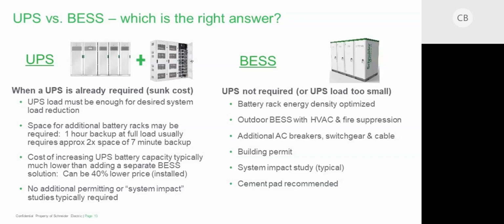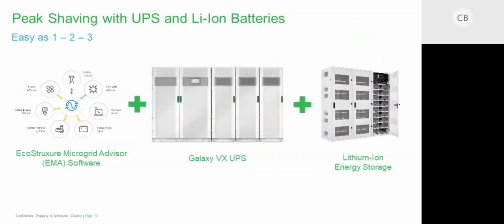So go to the next slide. So when we talk about peak shaving using lithium-ion batteries, the key is to have a software solution that's embedded that'll make the decisions for you. It's going to be looking at grid stability. It's going to be looking at when is the optimal time to do some peak shaving. When are you going to peak? On an August day at 2 o'clock in the afternoon is when we typically see that peak, and it's going to start throwing a portion of your load onto your UPS batteries versus relying 100% on your utility grid. Next slide.